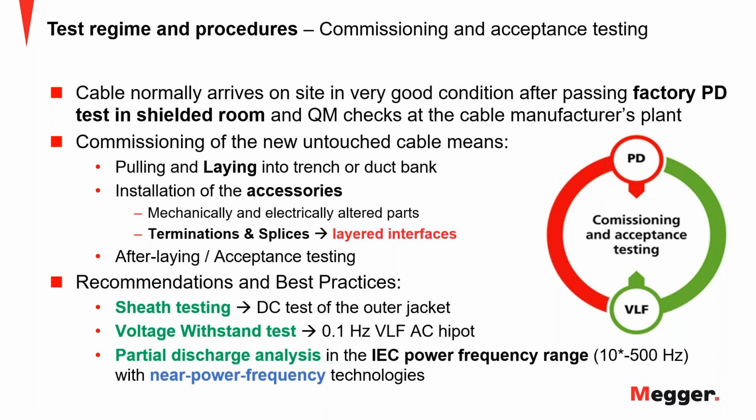That will find you all the gross defects, and this is kind of a safety test, so you can re-energize and it's not push and pray, it will not fail. And the new thing, which is, to be honest, nowhere in no standard in no country a mandatory test yet for commissioning, but we are on the way.